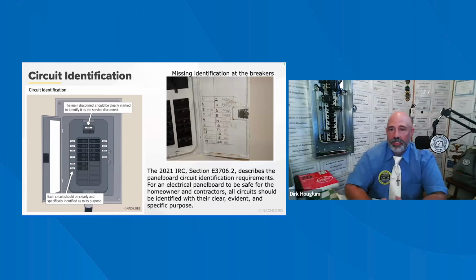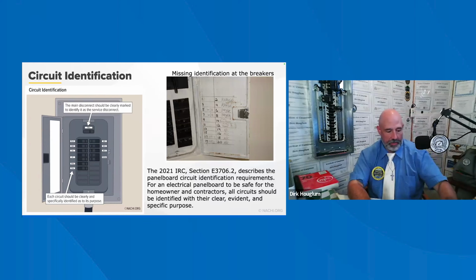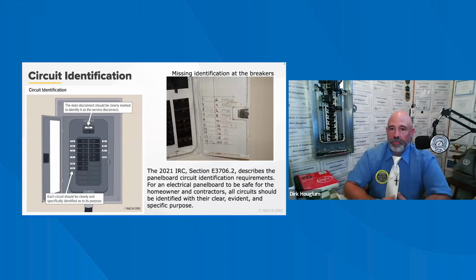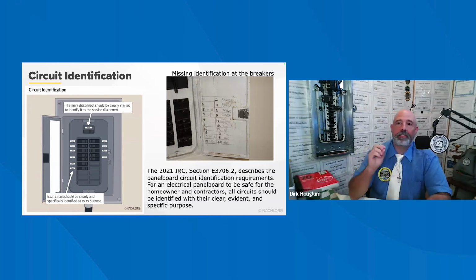Okay, let's see. Each circuit should be distinguished. We're going to keep going for another couple minutes here. Each circuit should be distinguished from all others. Spare circuits should be labeled accordingly. There should be a circuit directory installed on the face of the panel board door, inside the panel door, or in a location adjacent to the panel board. This requirement helps protect occupants and contractors when they're doing work and shutting off the electrical into certain parts of the house. Home inspectors may often find the panel board door with illegible markings that fail to identify the circuits specifically and accurately. If the markings at the breakers of the panel board are not legible, a code violation exists and the condition is a defect that needs correction.